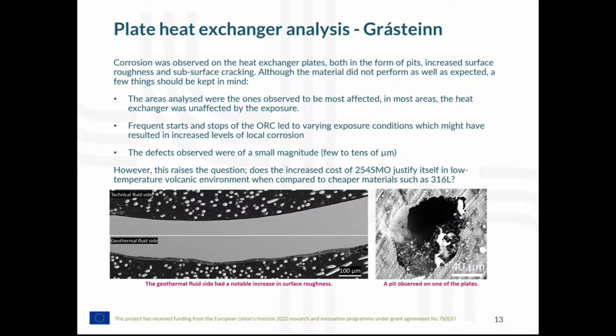Another thing to keep in mind regarding the plates at Grásteinn is that we had, in some cases, frequent starts and stops of the ORC and some potential atmospheric intrusion into the heat exchanger flow line, which can of course increase corrosion.